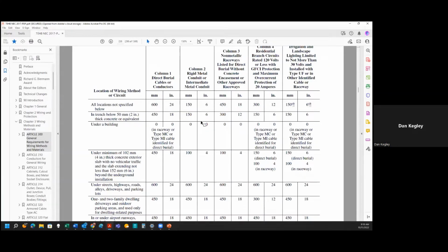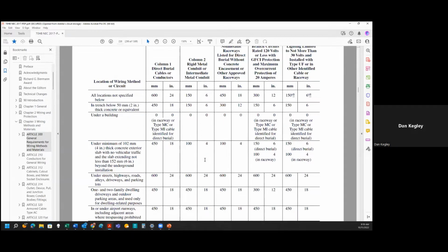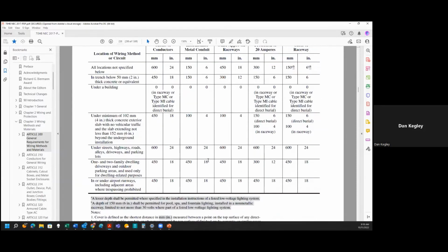If we go back down to where we look at 1 and 2 family dwellings, you see 18 inches again. So it didn't matter if you had just the cable, the UF cable, or the steel conduit, it's still an 18 inch burial depth, whether you had rigid metal conduit or had that cable. It's still 18 inches. Same thing, 24 inches.